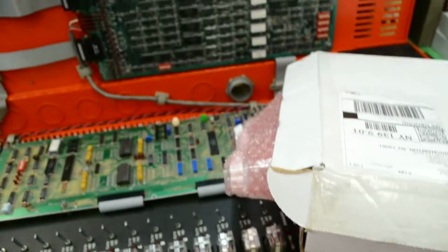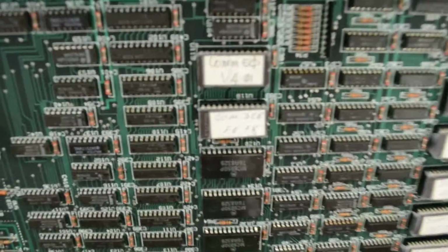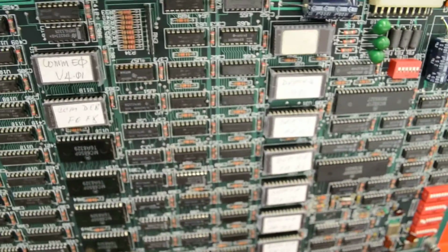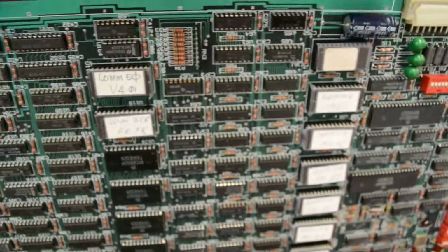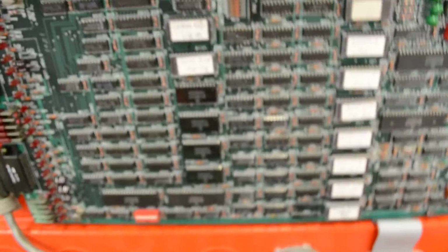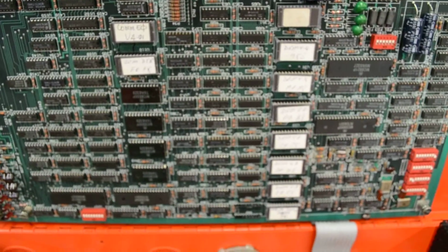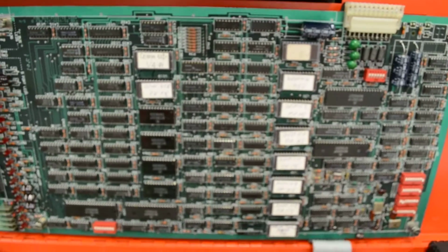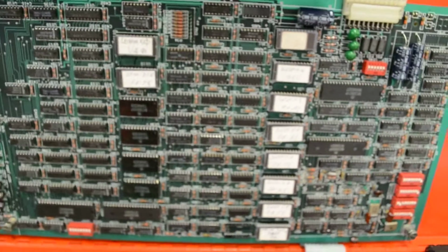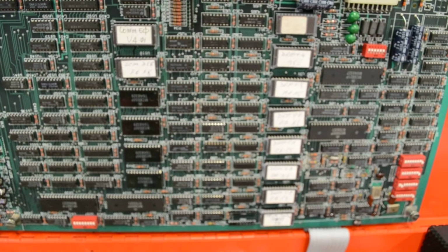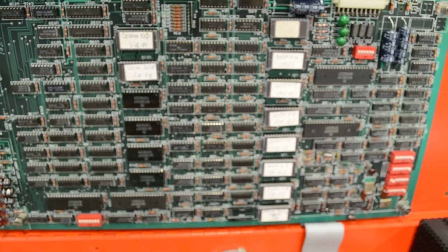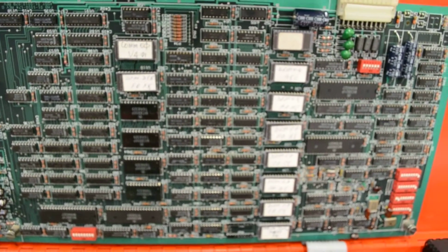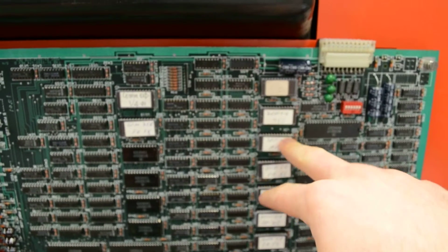Also discovered that in sending them a terminal session with the unit, the firmware is indeed version 4, as stated here in this tag, which is actually outdated because the newest version is 5.5. So, they recommended that I either pull all the PROMs off and they'll send updated ones, good updated ones, because these look to be corrupt. They're not recognizing all the available program space, and the software is giving me syntax errors. It just replies syntax error for valid commands.